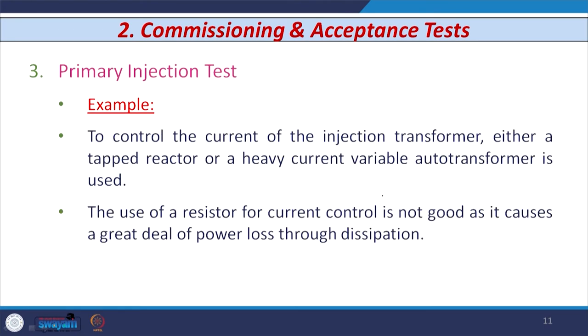To control the injection transformer, most primary injection test kits use a tap reactor. Sometimes a heavy-current variable auto transformer is also used, but most of the time a tap reactor is used. A resistor is not used because it would cause power loss through dissipation, so the tap reactor is used instead to inject the current into the coil of the relay.